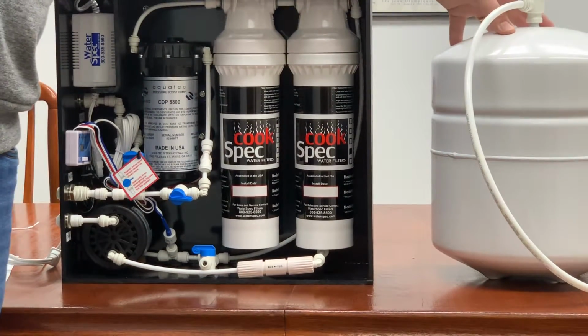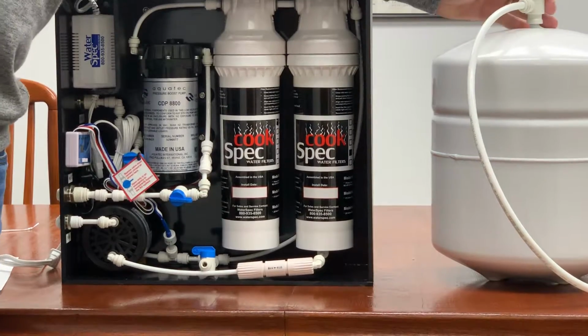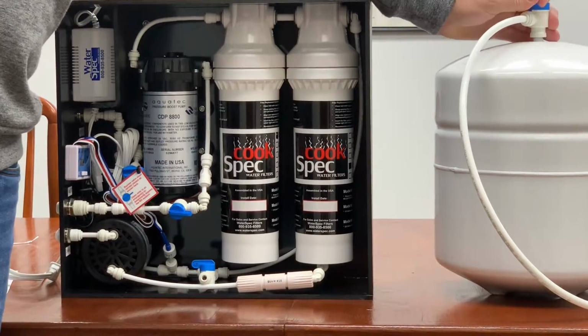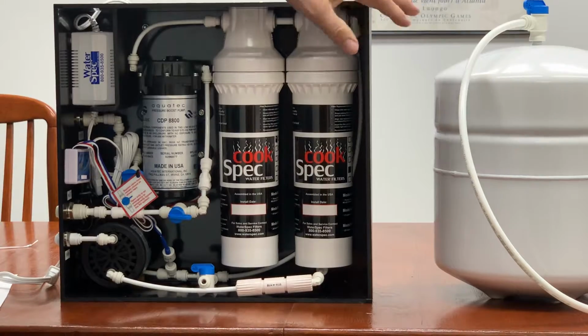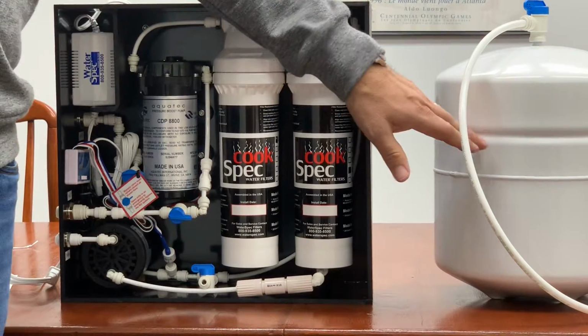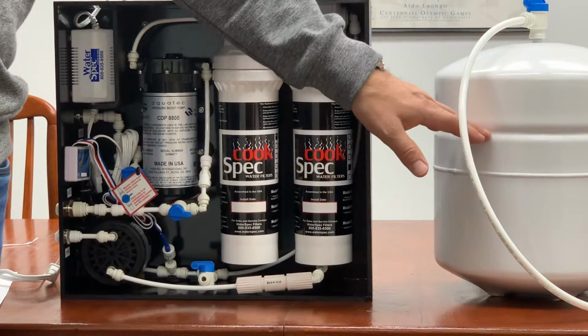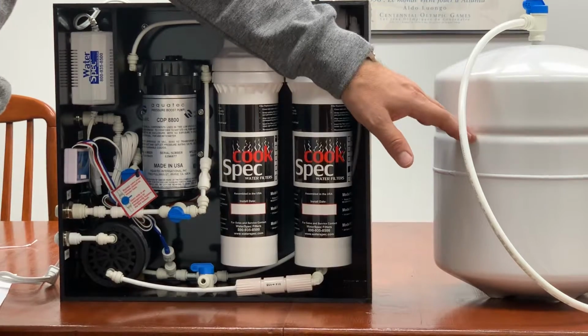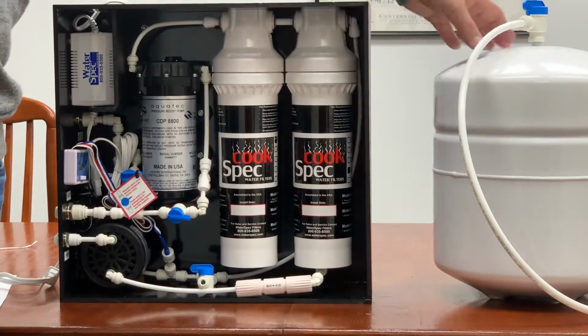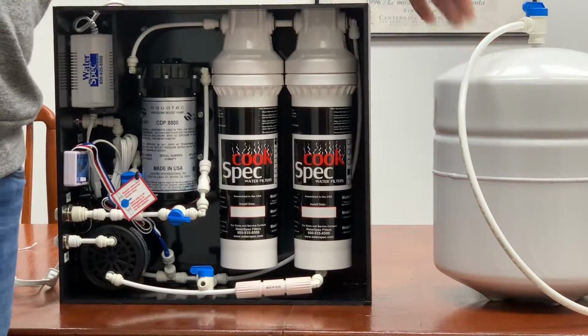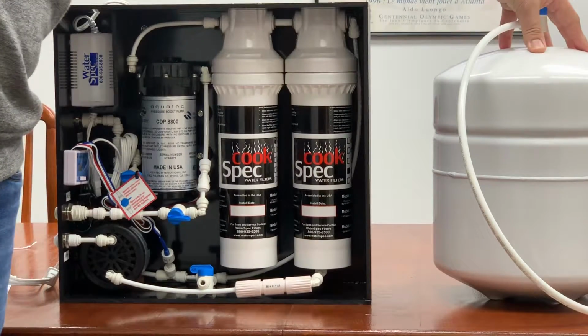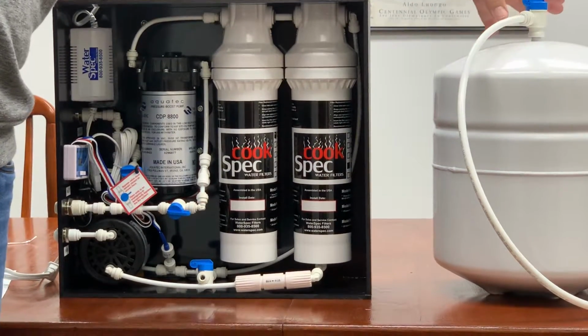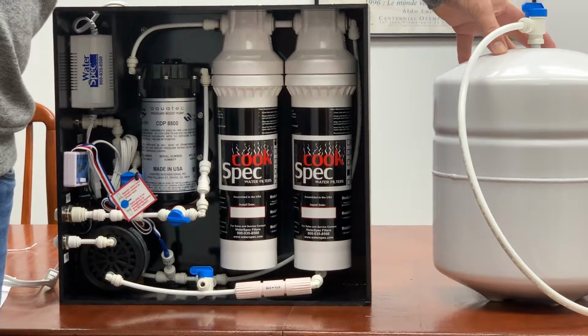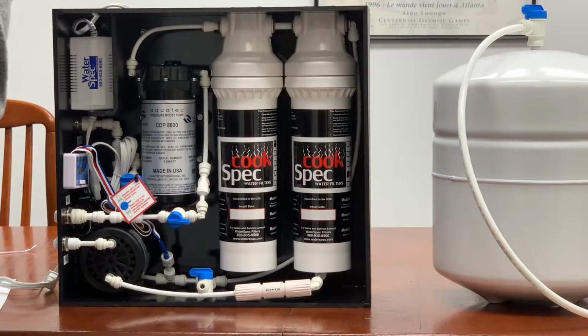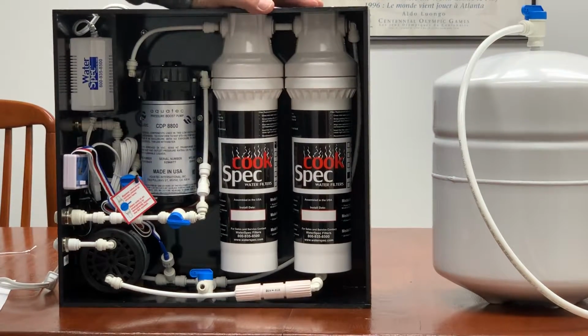This is a 3.2 gallon storage tank. It has its own valve on top of the tank that can be opened or closed. At 60 psi, there's a bladder in here that the tank will store roughly 2 gallons of usable water to be used at any given time. So when your combi oven asks for water, it's taking it from the storage tank. When the pressure drops on the storage tank, that's when the RO will start producing water again.